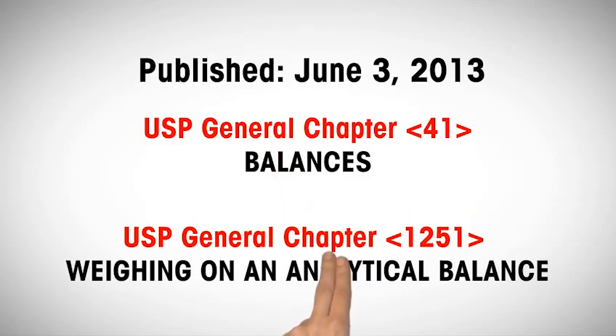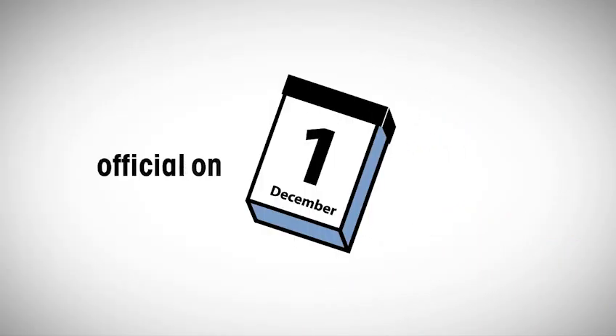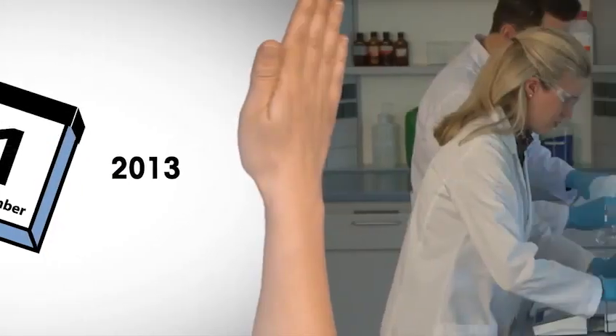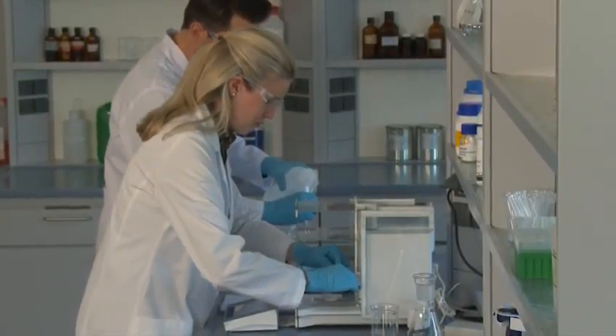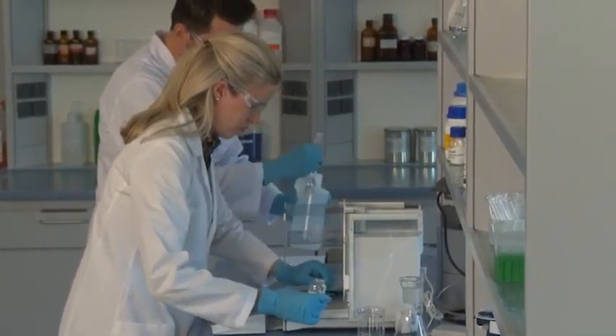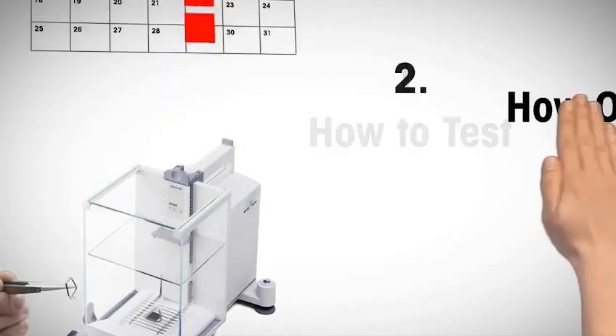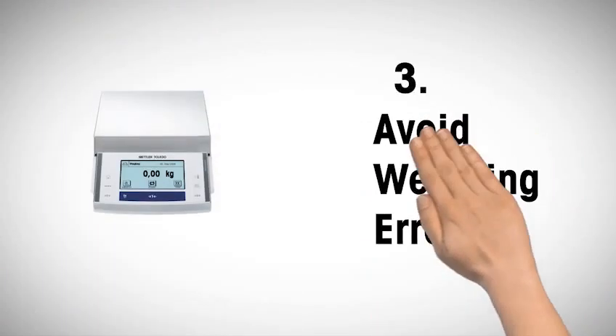On June 3rd, 2013, the United States Pharmacopoeia has published a second supplement to the USP 36 National Formulary 31. This video informs you about the relevant changes in the general chapters about weighing, namely USP General Chapters 41 and 1251, which will be official on December 1st, 2013. I'm going to show you the implications of these new chapters for the quality management of balances in 3 parts. How to test the weighing equipment, how often to test it, and how to avoid weighing errors.